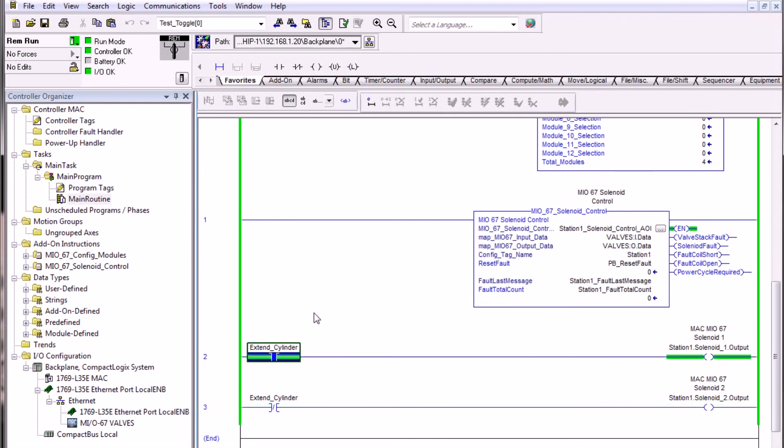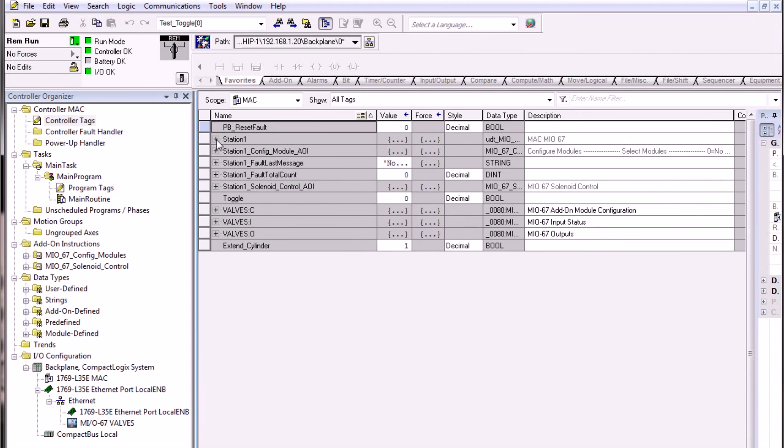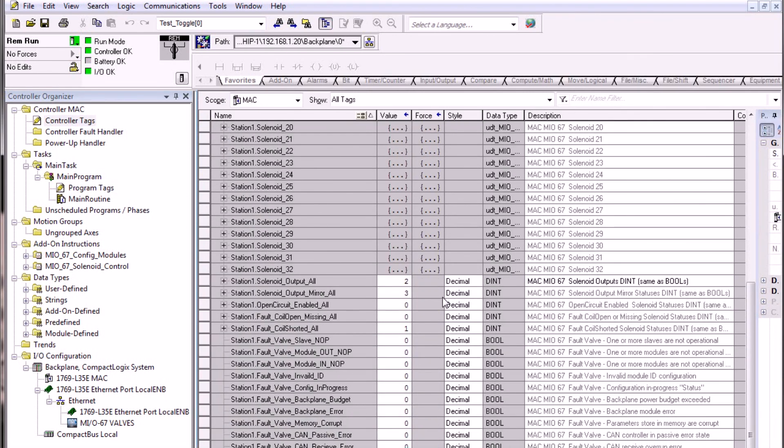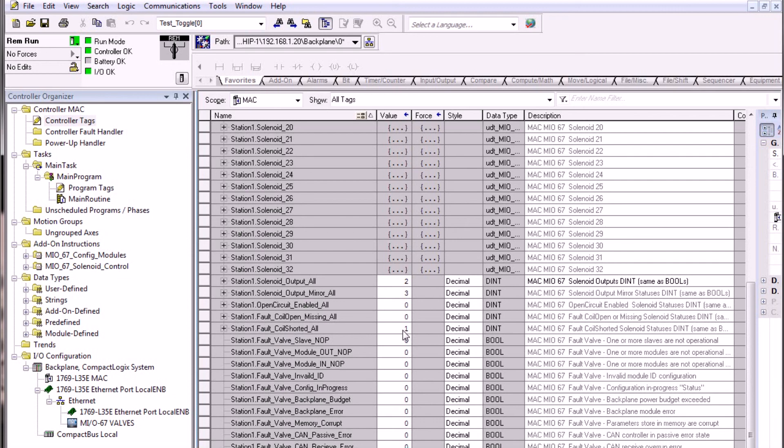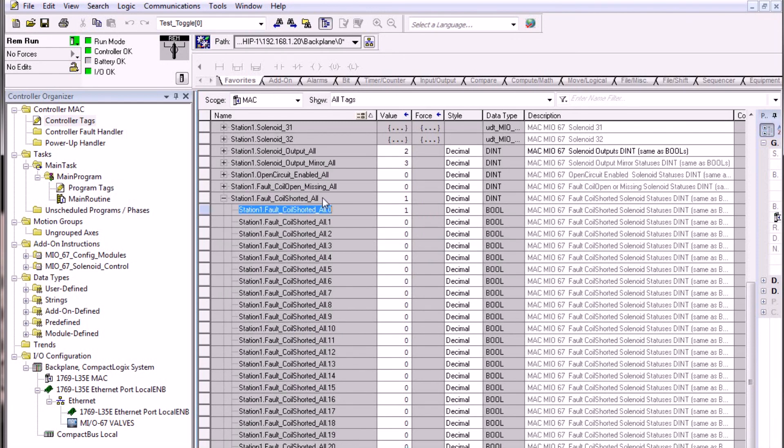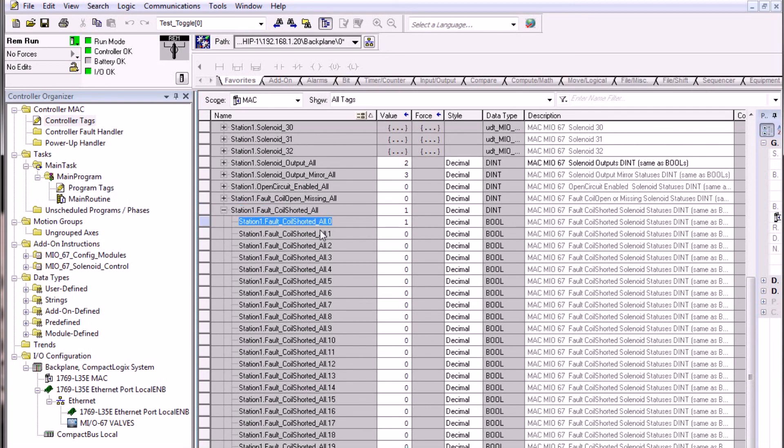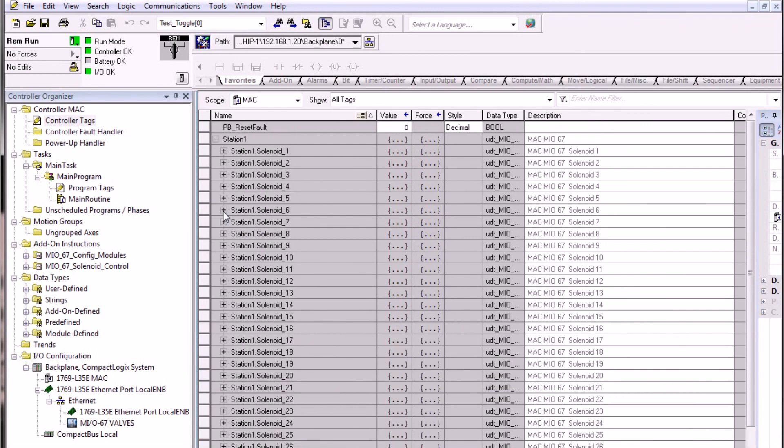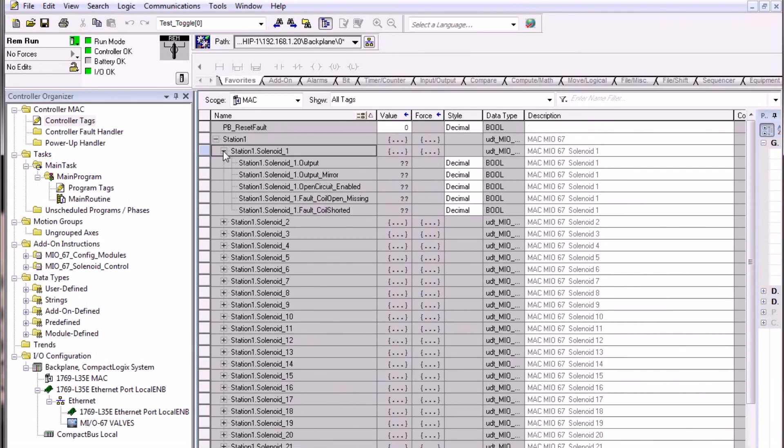If we create this fault once again, we can then go into the controller tags to see what some of the statuses are in the word structure here. We can now see the value of using the dint structure of the station one fault coil shorted all. We can see that there's a value of one. This indicates that one of the solenoids is shorted. We can then expand this tag out to see which solenoid has been shorted. Here, since bit zero is solenoid one, we see that flag number one is set. We should also be able to see that in the boolean structure up here by station one solenoid one, and we can see that the fault coil short flag is now turned on.